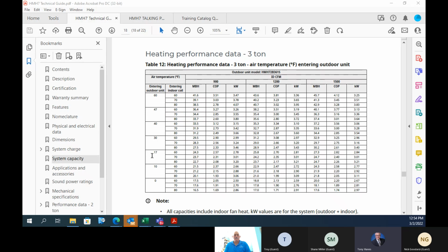Now, if you come down to 17 degrees, which, by the way, Tony, is the other AHRI rated point. So to your point, this table covers more than just AHRI, because AHRI is 47 and 17, but let's track that over and see what we're doing at 17 degrees. At 17 degrees, same CFM, same 70 degree entering airflow, you're getting 24,200. That is 68% of the total capacity at 47 degrees. So you're still getting 68%.